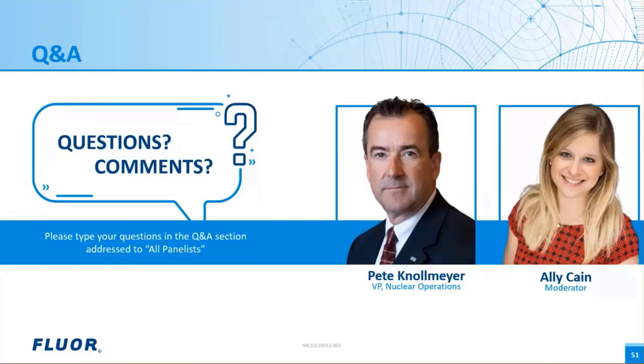Next question is, has the passive safety been tested in prototypes, or is it still theoretical? So the passive safety has been tested in prototypes. As I mentioned, there's the 1/3 scale thermal hydraulic test facility in Corvallis. So obviously we're not using nuclear fuel. That's an electrical powered simulated reactor, but you can simulate all of the flows and heat transfer characteristics and verify the codes we are using. So to the extent that any reactor or heat transfer device is proven before it's built, yes, it's proven.